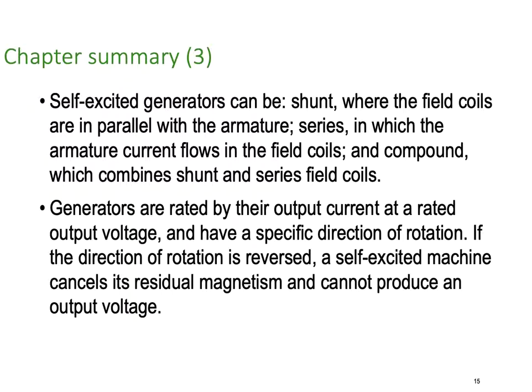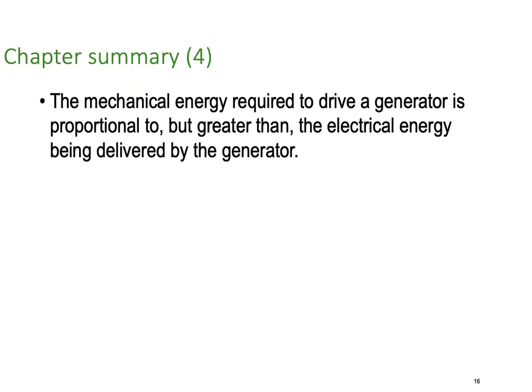So if you get the rotation on a DC machine the wrong way, it will cancel out its own excitation and won't ever build up to restart. The mechanical energy required to drive a generator is proportional to, but greater than, the electrical energy being delivered by the generator, because of the losses.